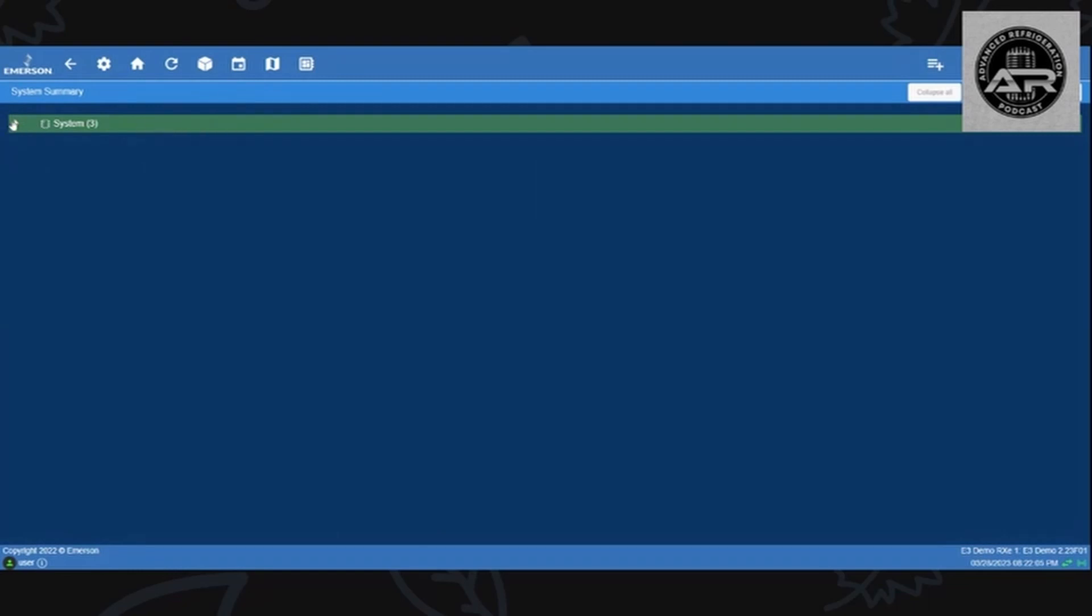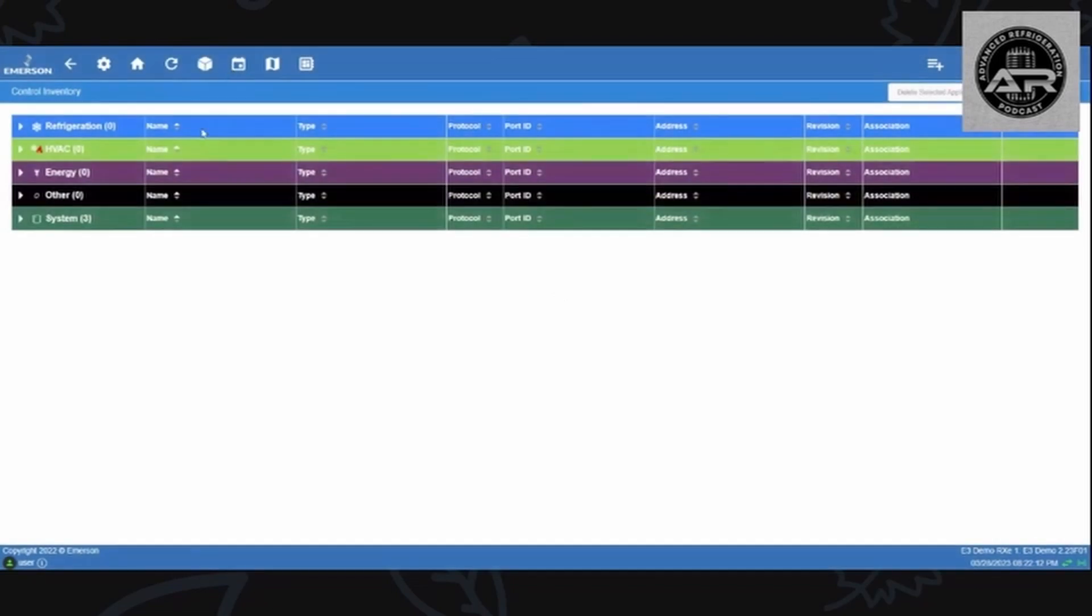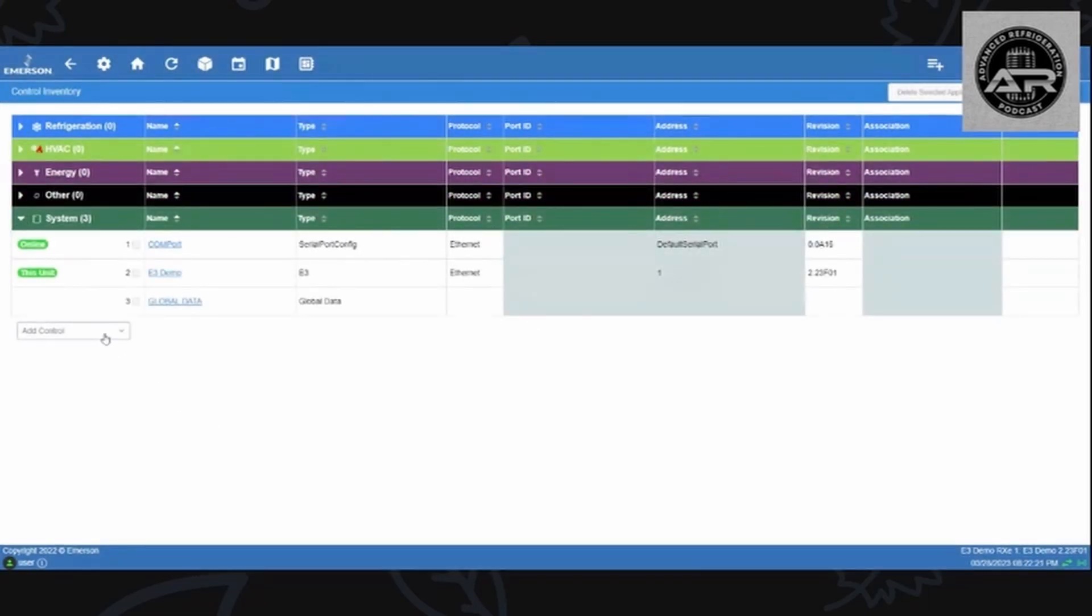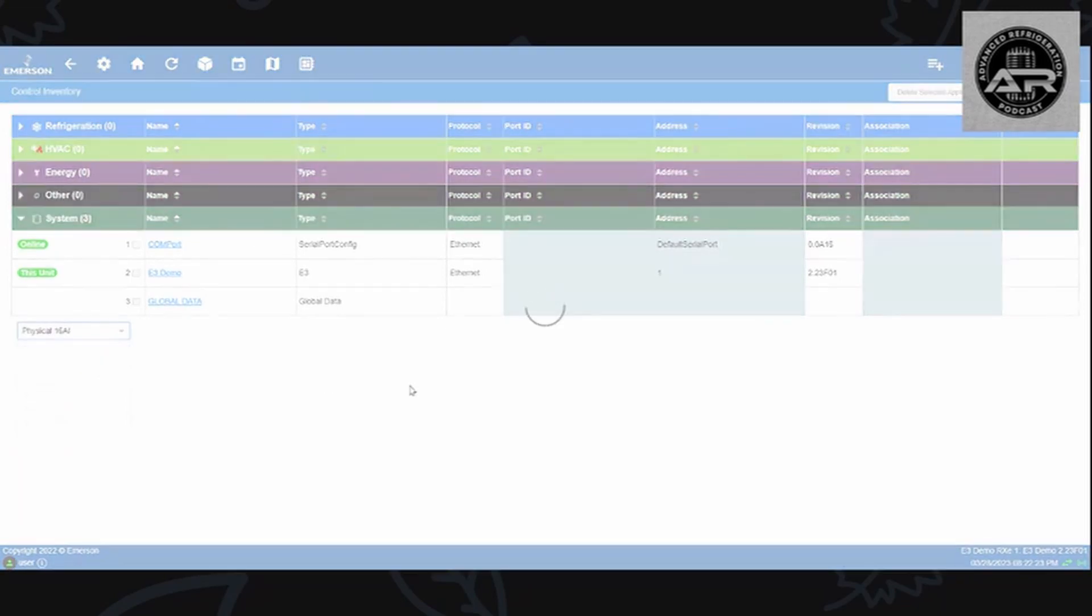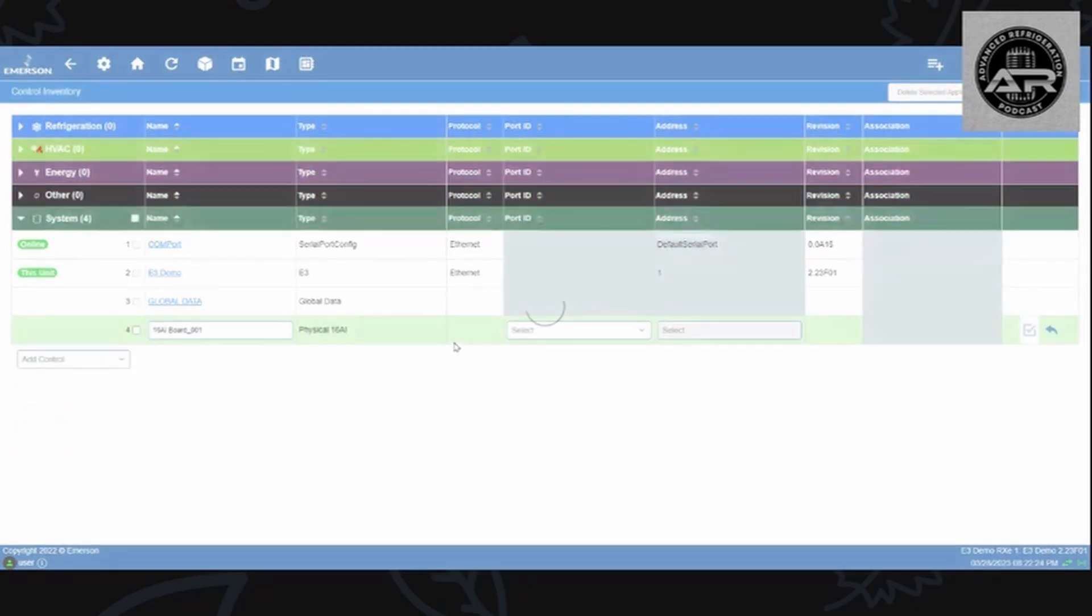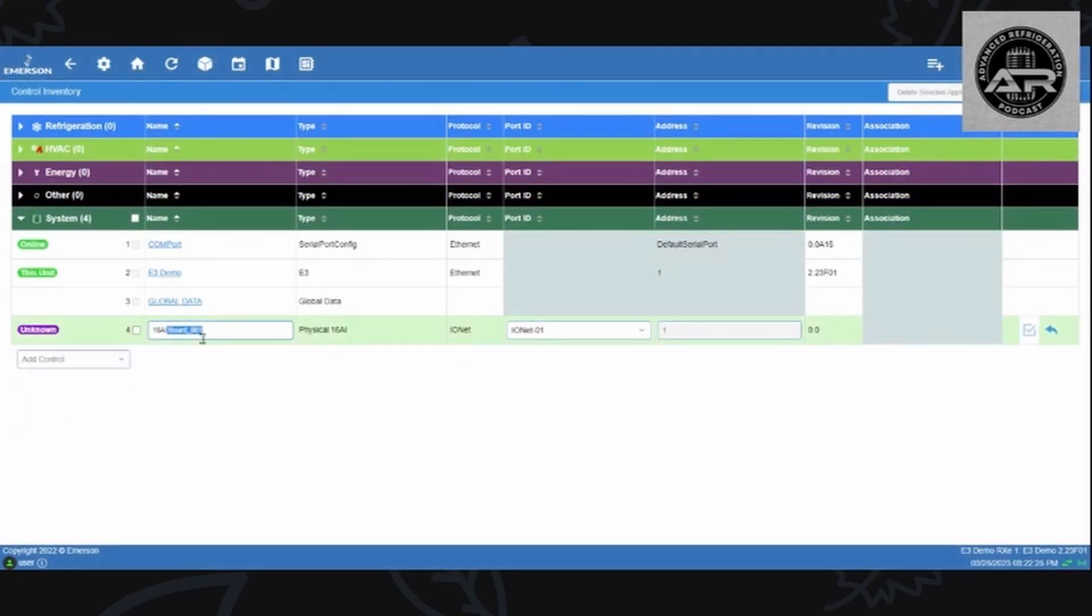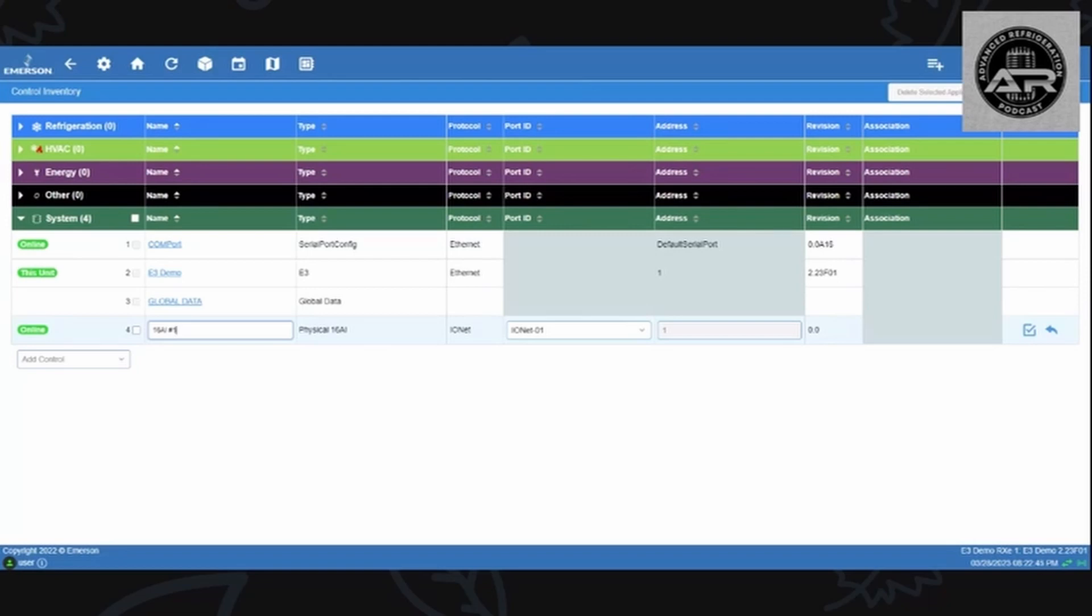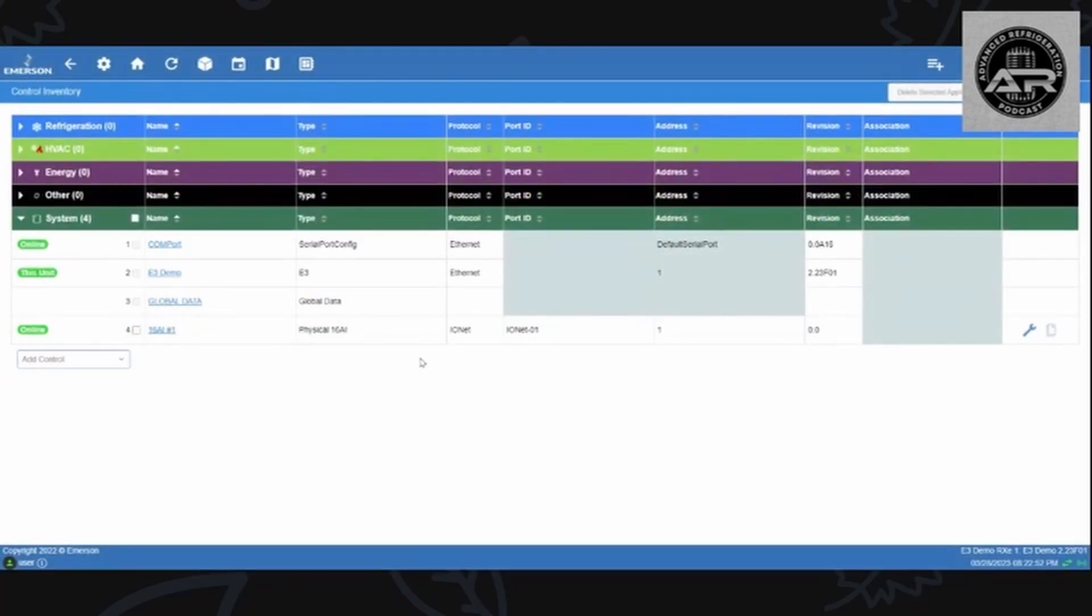The home page brings me to the initial tile screen. Every category will have a drop down menu on the left hand side if you want to add components. We're going to do the control inventory which is this cube thing. Let's say I'm going to add some boards first. Drop down menu, what do you want to add? Let's pick a 16 AI. The type of board it is, the next column over is going to be physical 16 AI, its protocol is IO Net, the port ID is IO Net 1 which we saw was configured to com port 4, and address 1 is what it starts off with. We're just going to hit the check mark on the right side, it's already online, popped up pretty fast.